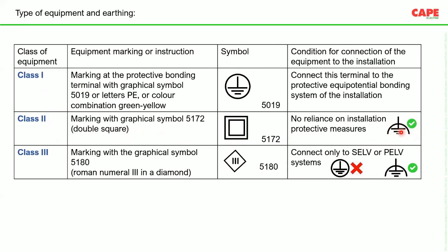Here on the right side, the symbol shows functional earthing. Class 3 devices operate at a very low voltage, sometimes a voltage which cannot create a shock hazard. In this case also, protective earthing is not required, but functional earthing may be required. So whenever you make a protective equipotential bonding, first you should also consider the type of equipment which you are going to use. And for functional earthing, the recommended color is cream.